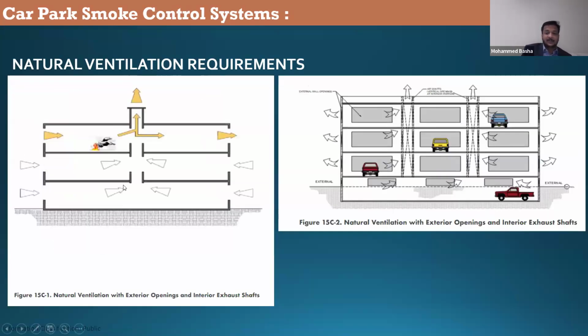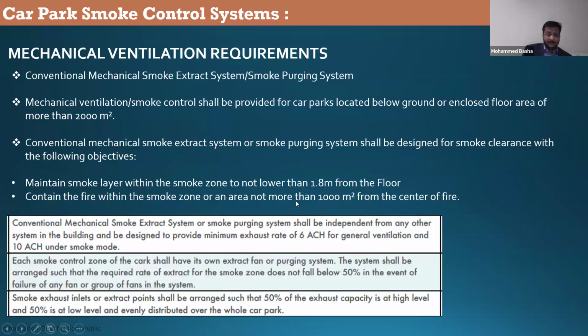You can see this is also acceptable: natural ventilation with exterior openings and shafts. It's all by QCDD. You do not need any kind of fans, but subject to the depth requirements and the area requirements. Mechanical ventilation system. This is the fans. By using fans, we have two types, as you know very well: conventional smoke extract, which is done by a ducting system, and impulse ventilation, which is by using jet fan systems.